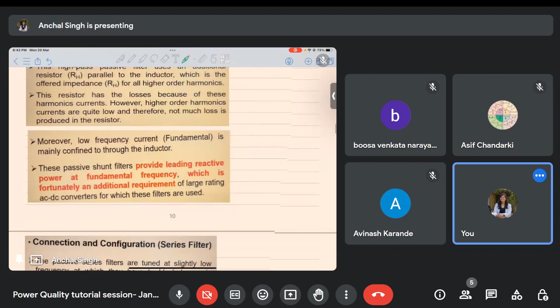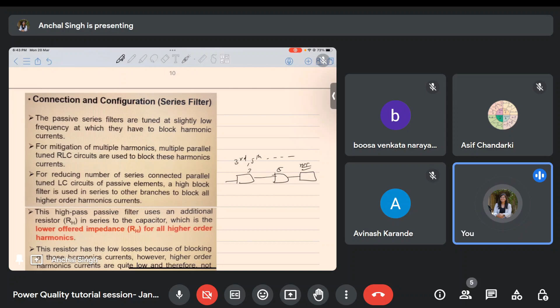So when we talk about series filters, passive series filters are tuned at a slightly low frequency at which they have to block the harmonic. The same principle that we just saw for shunt also applies to series filters. And for reducing the number of series connected parallel tuned LC filters of passive elements, a high pass filter is used in series. Suppose I have a system in which third, fifth, and all the higher order harmonics are present, then I will put one filter for the third harmonic, one for the fifth, and one high pass filter. Instead of putting separate filters for seventh, 11th, and 13th, I just put one high pass filter. That will take care of all the higher order harmonics.